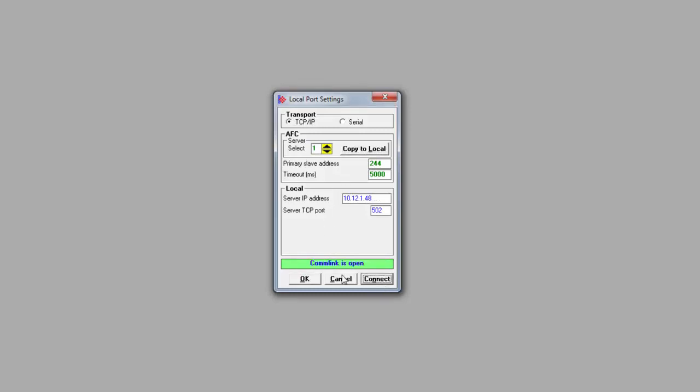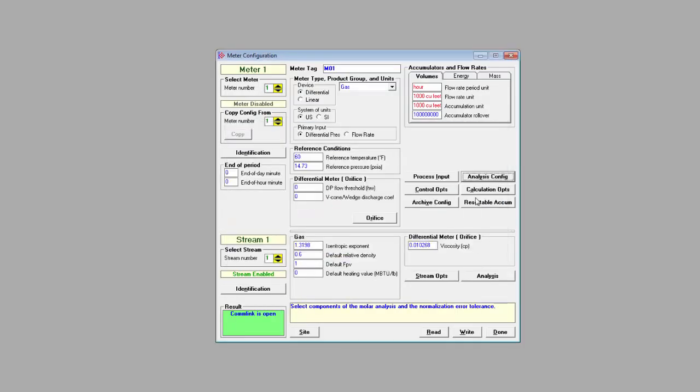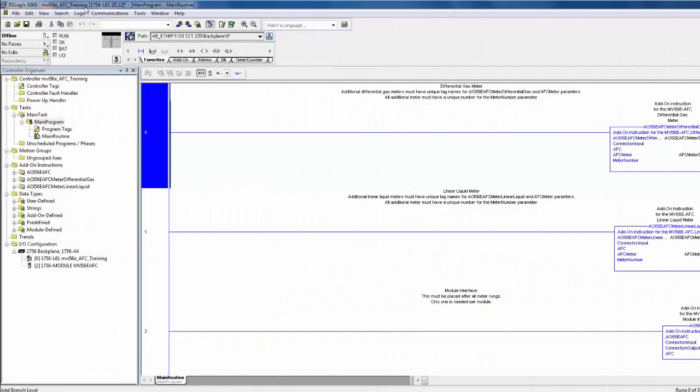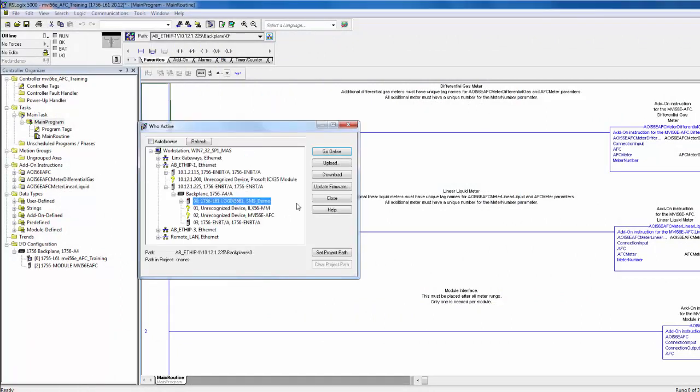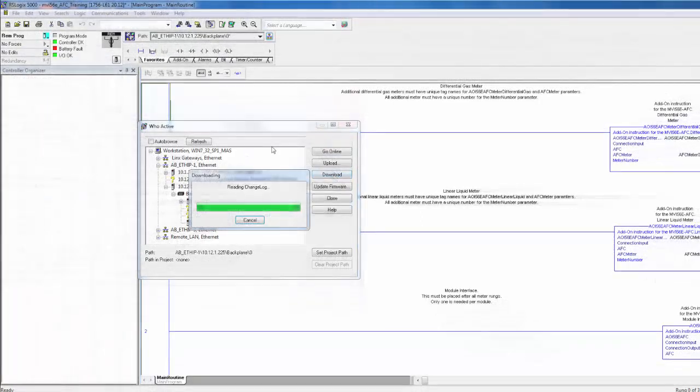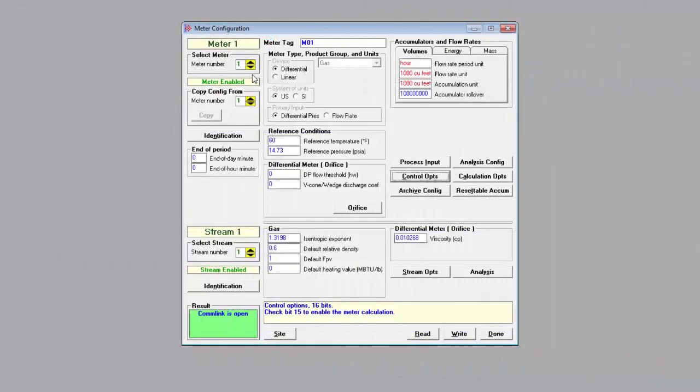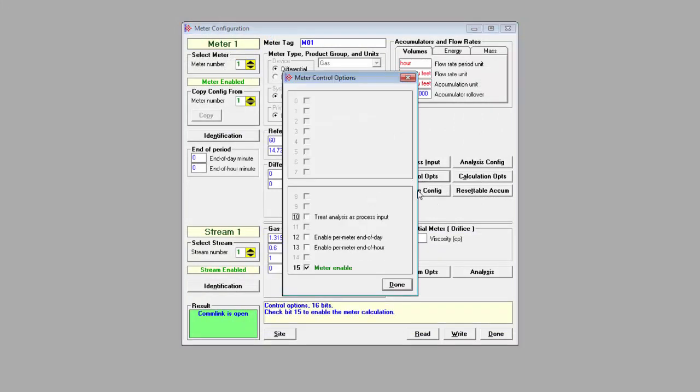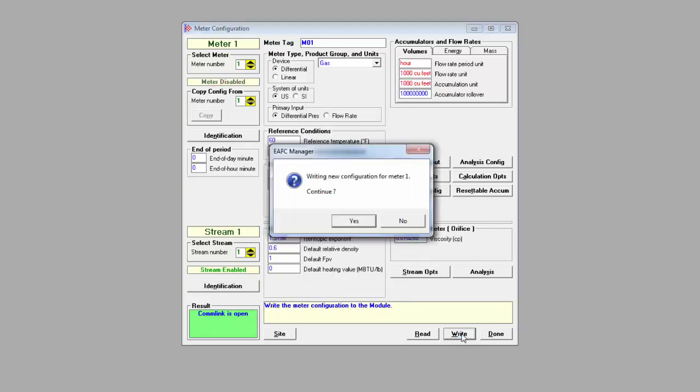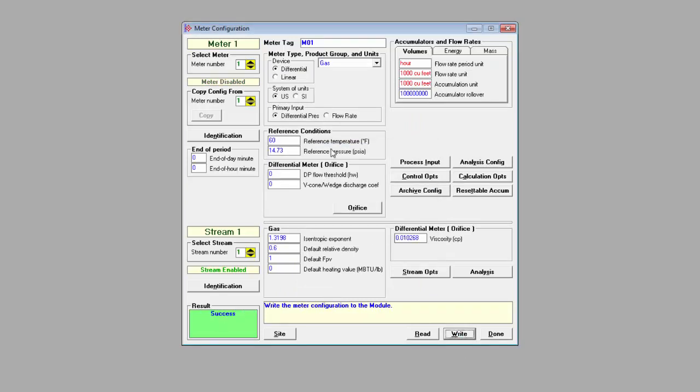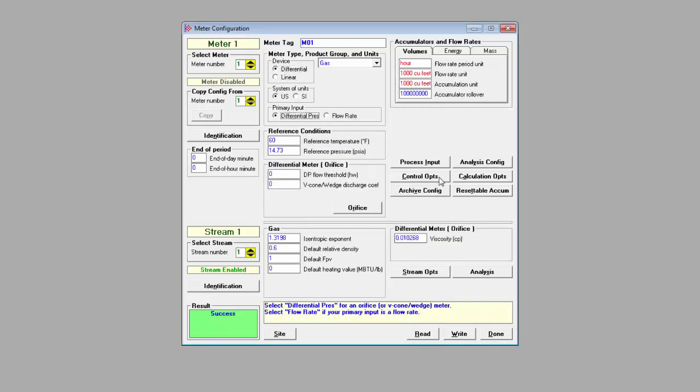At this point, our configuration is complete. We can return to RSLogix, go to WhoActive and download the project to our Rockwell processor and set the program to run mode. Just a tip, once your meter is enabled, you will not be able to change the meter type, the product group, etc. To make changes to this section, you'll have to open up Control Options and deselect Module Enable. You would then write this change to the AFC module in order to deactivate it. Then you'll be able to edit the meter configuration again, set the module back to Enable and write that.